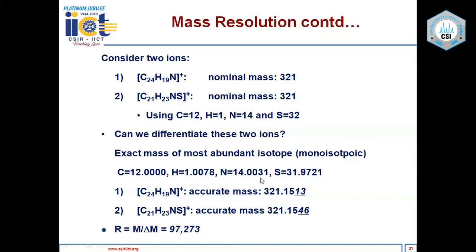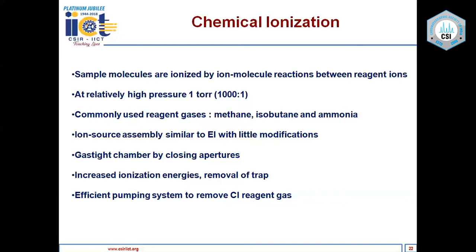Accurate masses are well documented in textbooks. When two ions differ at the ppm level, the resolution required to separate them can be as high as 97,000. Essentially, each molecular formula has a unique accurate mass, and high resolution mass spectrometry uses this to derive elemental compositions.